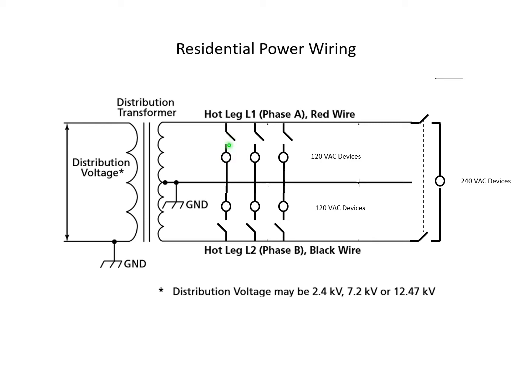And on the 120 volt side, you'll have one breaker for each item that you've got wired into your house. Sometimes you'll string several outlets on one breaker. And then to get 240 volt devices over here, you'll have two circuit breakers. They're side by side physically in the box, and we'll take a look at that. But they are mechanically connected so that if one trips or one is opened manually, then they both open up and disconnect the 240 volt device from the incoming line.